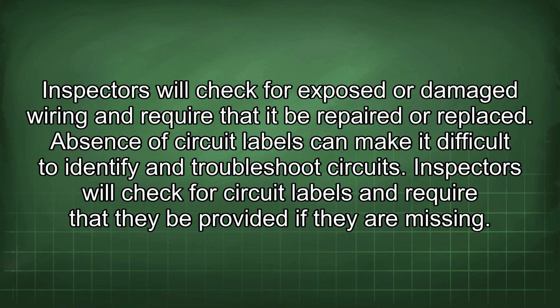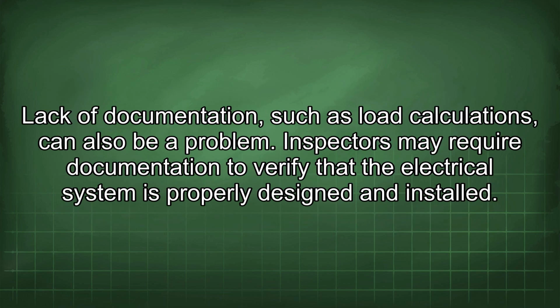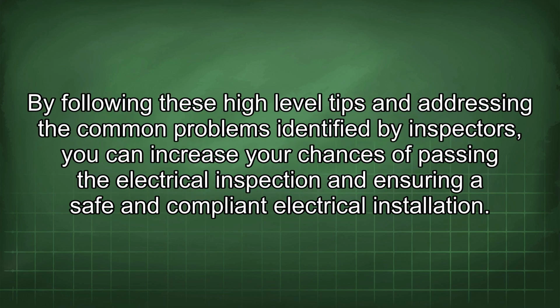Absence of circuit labels can make it difficult to identify and troubleshoot circuits. Inspectors will check for circuit labels and require that they be provided if they are missing. Lack of documentation, such as load calculations, can also be a problem. Inspectors may require documentation to verify that the electrical system is properly designed and installed. By following these high-level tips and addressing the common problems identified by inspectors, you can increase your chances of passing the electrical inspection and ensuring a safe and compliant electrical installation.